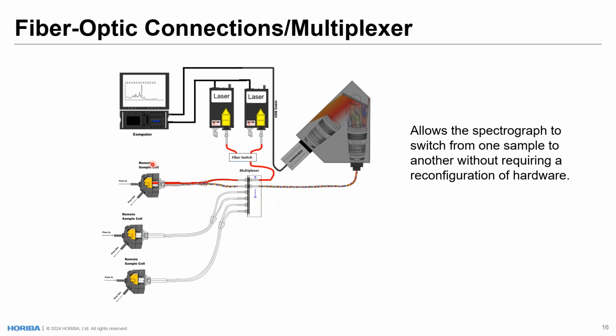So for example, in a typical collection with an online analyzer, we have 2 different redundant lasers installed in all of our online Raman analyzers to help extend the lifetime of the lasers, as well as offer a more secure backup where there is much less downtime, if any downtime, if one of the lasers were to fail, because there's a second laser that can just pick right back up where the other one left off.